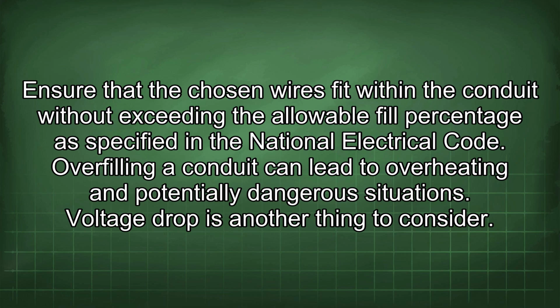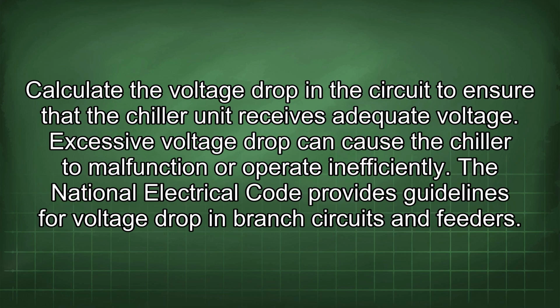Voltage drop is another thing to consider. Calculate the voltage drop in the circuit to ensure that the chiller unit receives adequate voltage. Excessive voltage drop can cause the chiller to malfunction or operate inefficiently. The National Electrical Code provides guidelines for voltage drop in branch circuits and feeders.